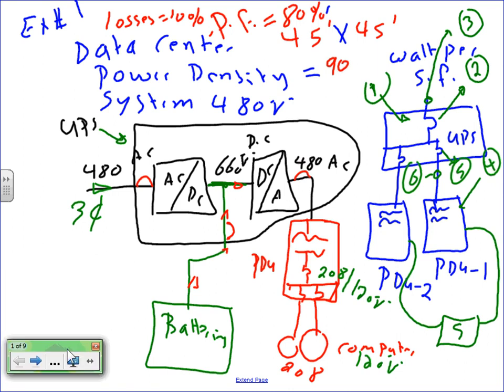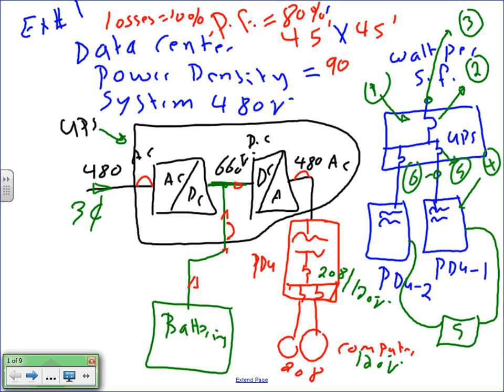Okay, Chris, take this. This is a UPS system, and you guys are sizing a UPS system. The following you need to understand, those of you who were here when we did a UPS system, this is very similar. The first thing you need to understand about the UPS system: I have a data center. The power density is given as 90. I'm giving you a power density of 90. System is 480. I need a power factor of 80, and the area of the data center is 45 by 45, a square room.